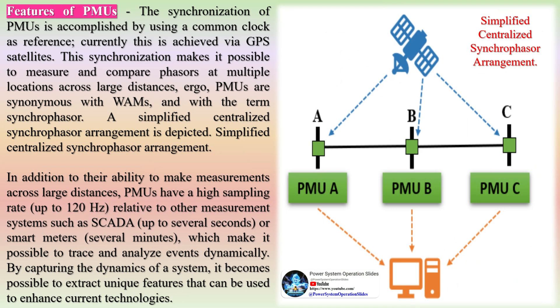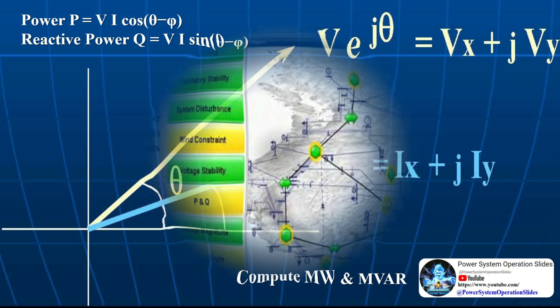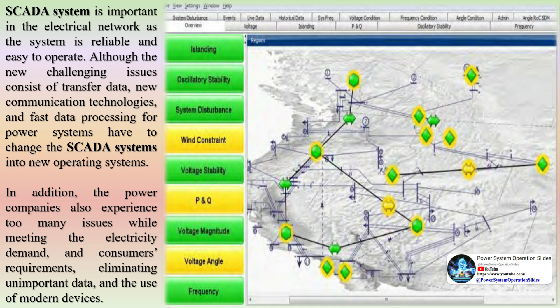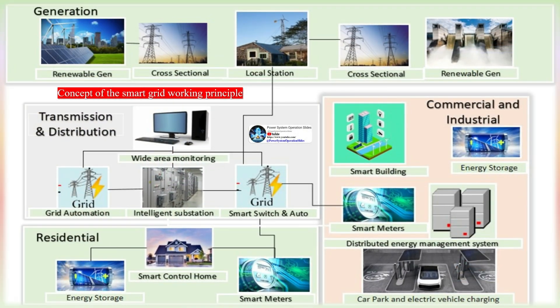The synchronization of PMUs is accomplished by using a common clock as reference, currently achieved via GPS satellites. This synchronization makes it possible to measure and compare phasors at multiple locations across large distances; therefore, PMUs are synonymous with WAMS and with the term synchrophasor. A simplified centralized synchrophasor arrangement is depicted. Different important parameters are included in the operation of PMUs such as wide area management systems (WAMS), phasor data concentrators (PDC), and GPS.